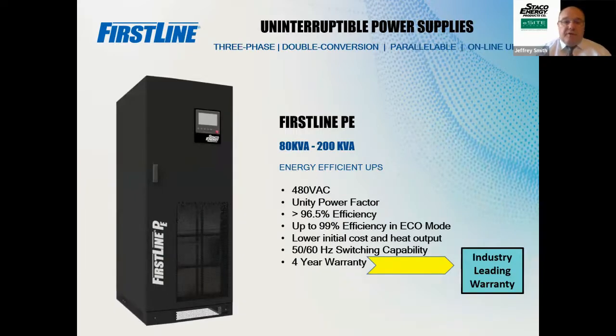The PE series, 80 through 200 kVA. This is a transformerless UPS. It's 3-phase, 3-wire in and out. There is no neutral for this. This is designed so you can put this in a data center or put it over to a power distribution unit that has transformers that you can step down to your 120/208. All right, next slide.